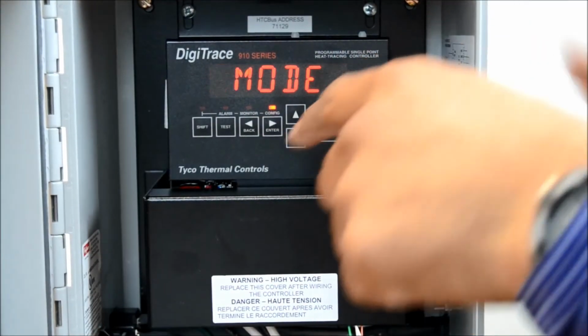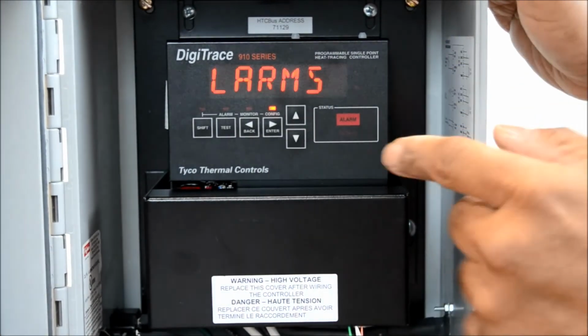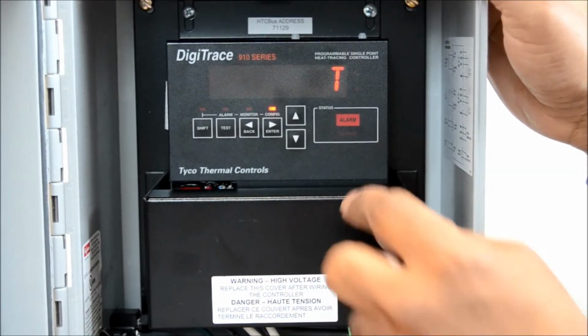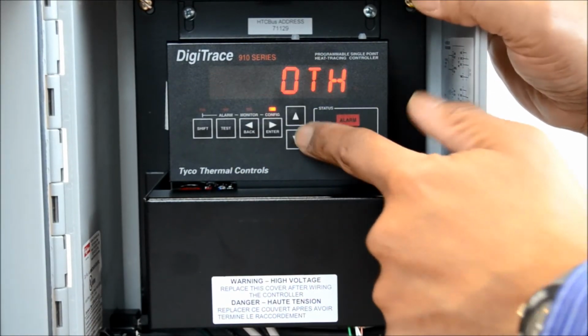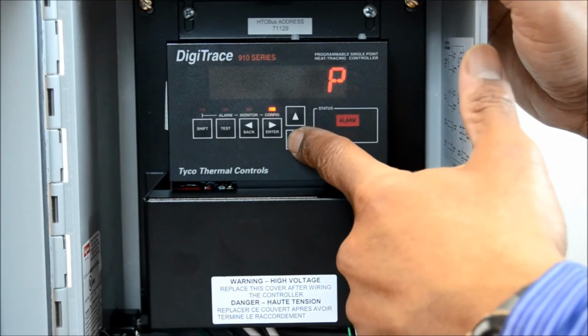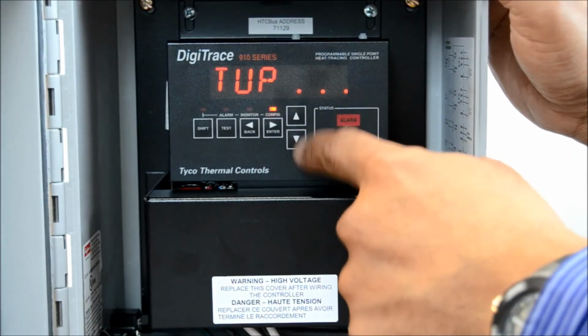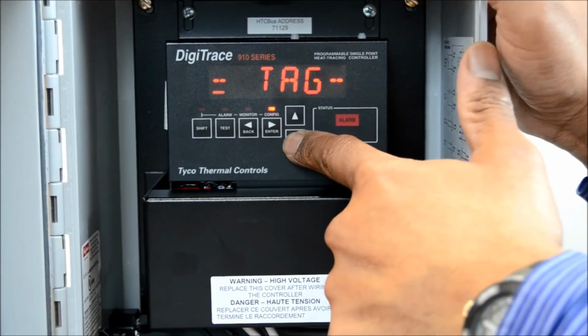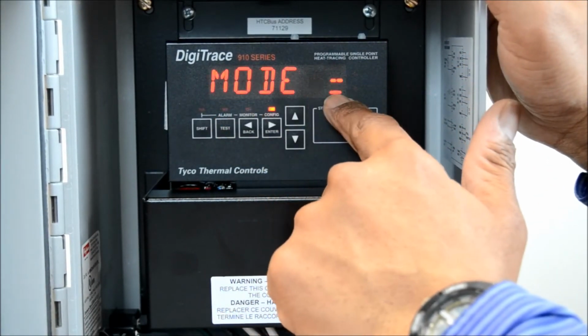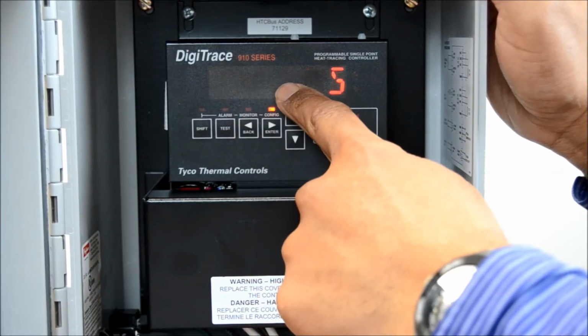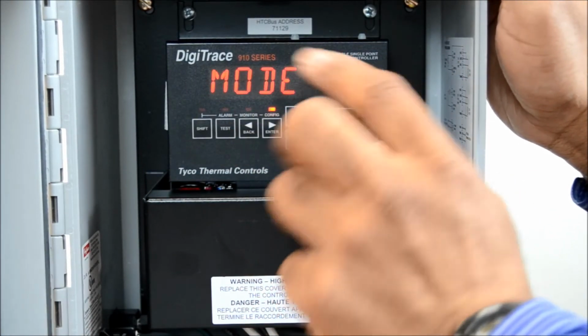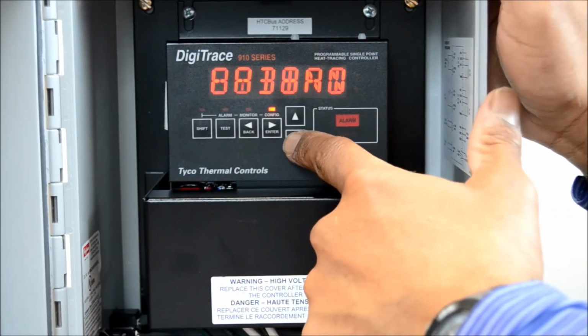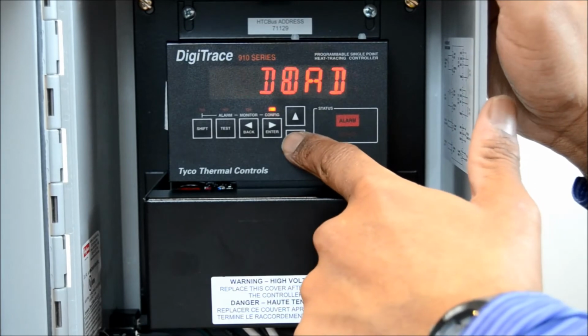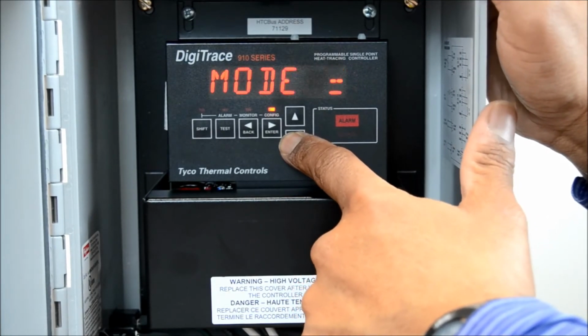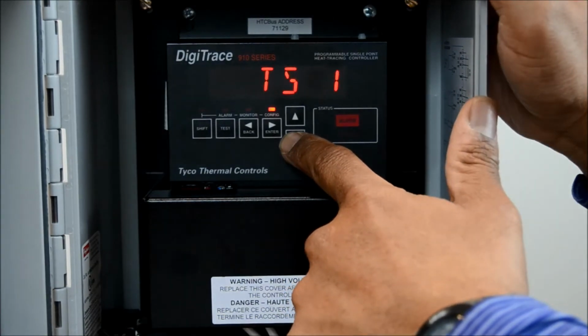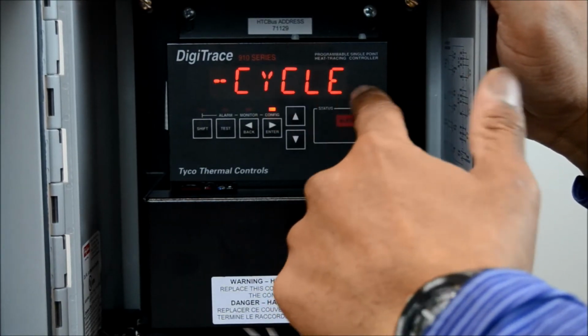But getting into the advanced, you will get into changing temperature alarms, and you can change many different temperature alarms. You can change some other alarms. You can go into point setup, which I like to do, and I go down and you can switch the control mode. Remember before I told you about deadband and proportional mode, so you can change that in this function here. You can continue to go down. The deadband is at 5 degrees, like I mentioned before. You can change the temperature fail mode, but what I'm going to do is go down to the auto cycle.